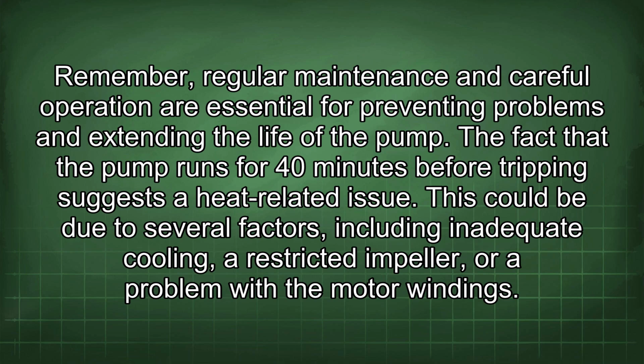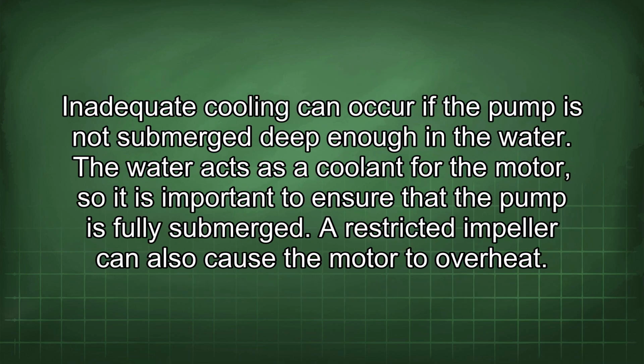The fact that the pump runs for 40 minutes before tripping suggests a heat-related issue. This could be due to several factors, including inadequate cooling, a restricted impeller, or a problem with the motor windings. Inadequate cooling can occur if the pump is not submerged deep enough in the water. The water acts as a coolant for the motor, so it is important to ensure that the pump is fully submerged. A restricted impeller can also cause the motor to overheat.